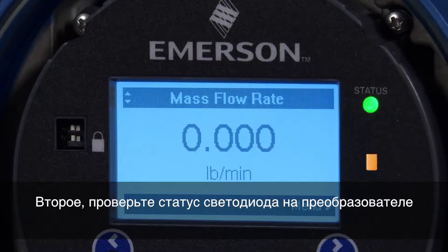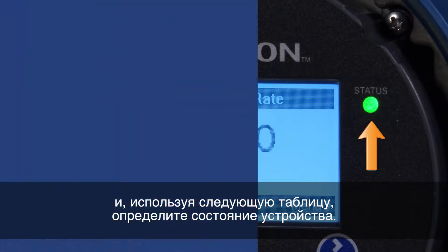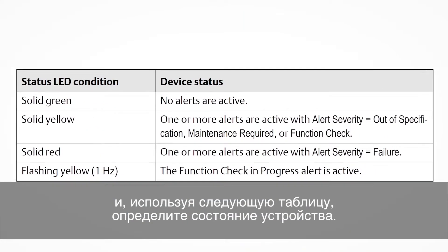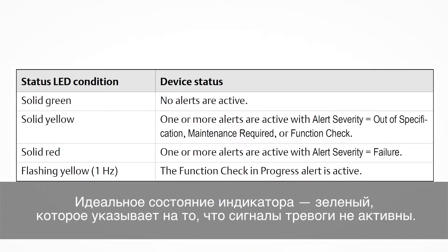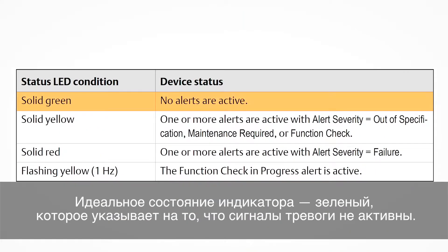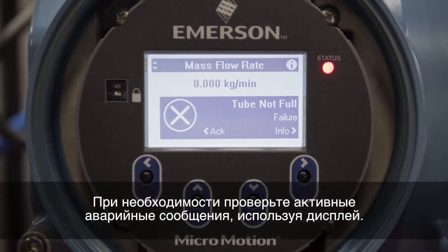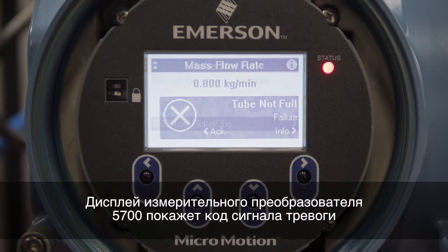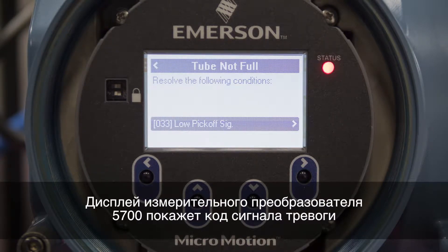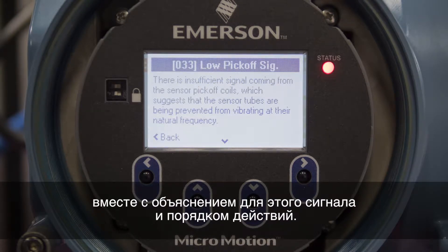Second, check the status LED on the transmitter and use the following table to determine the device status. The ideal LED status is solid green, which indicates that no alerts are active. If necessary, check the active alerts using the display. The display of the 5700 transmitter will show the alert code along with an explanation for the alert and the course of action.